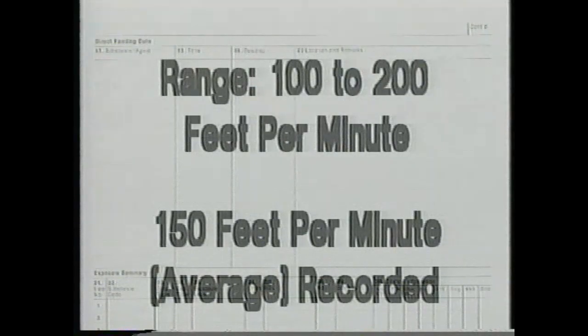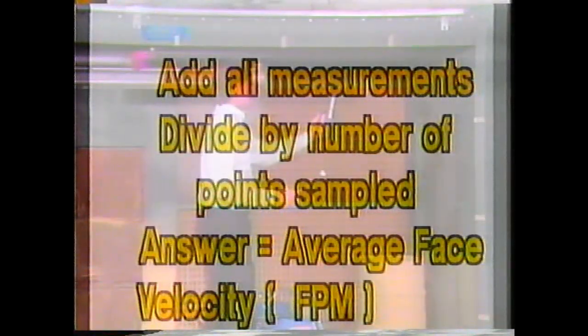For example, if the range is 100 to 200 feet per minute, 150 feet per minute would be recorded on the OSHA 93 form. Now remember, while taking measurements, avoid placing your body or other obstructions near the area being measured. Such obstacles will affect the movement of the airflow being measured. When taking measurements for the average face velocity at a spray booth, for example, an average velocity can be determined by dividing the face area of the booth into sections of equal area and measuring the airflow at the center point of each section. After recording velocity measurements at each point, add up all the measurements and divide the sum by the number of points or sections used.